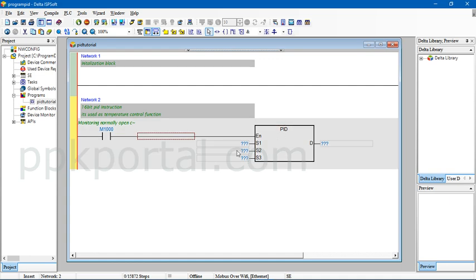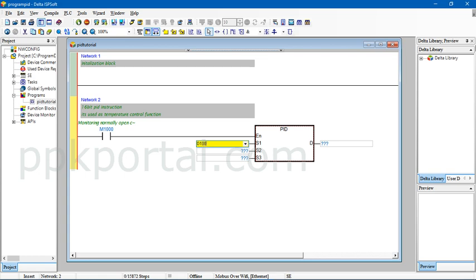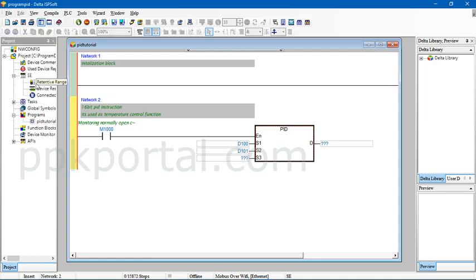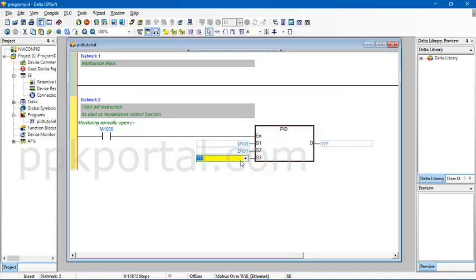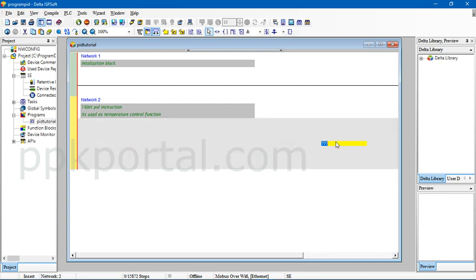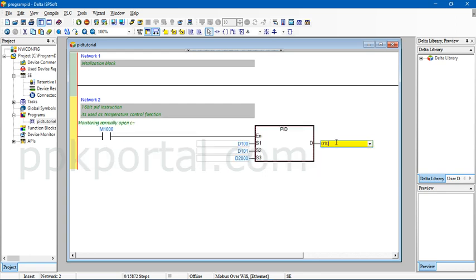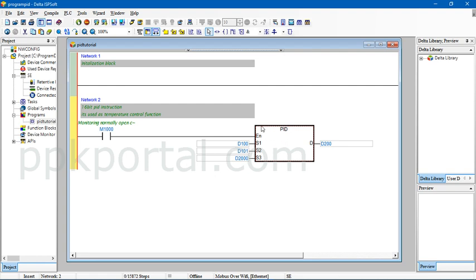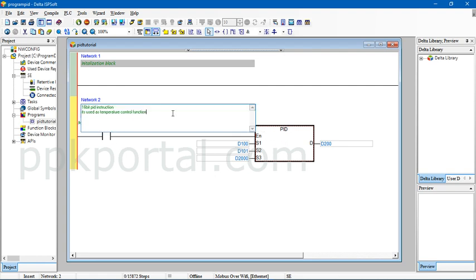Let me give some values here. For the set point I'm using D100, for the process feedback I'm using D101. If you go to the PLC icon, go to the retentive range and click on D, you will see the blocks which are available with retentive range. I will start with D2000, and the output let it be D200.